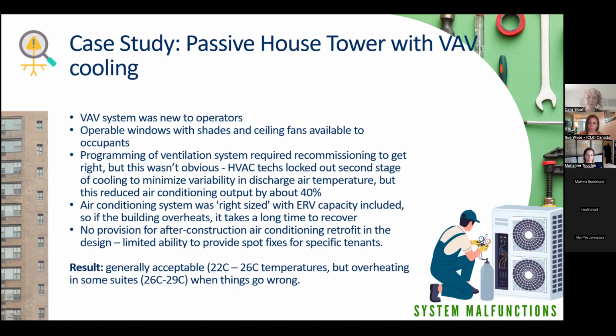So we sized the air conditioning per good practice using the passive house tool, 8760 modeling, future weather files, and looking at occupant behavior. We believed we'd created something that wouldn't have overheating problems, even though we could only add as much air conditioning as was permitted within the existing electrical supply envelope. We talked this through with the building owners, who knew this wasn't going to be a fully air-conditioned building when we turned it over.